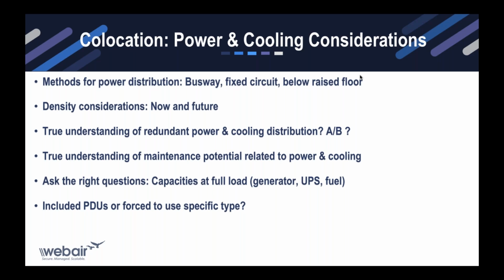In older facilities, even though there's a raised floor for cooling purposes, that raised floor would also be used for branch circuit and power distribution. If the data center is distributing power under the floor, I'd ask them to lift up some floor tiles so I can see what's going on under there. If you see tons of conduit and cables, that's all volume that was originally reserved for actual cold air. If it's being consumed by conduit and cables, the facility won't be able to achieve the density it was designed for.